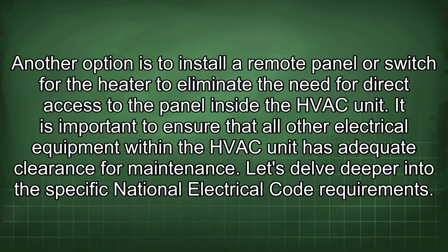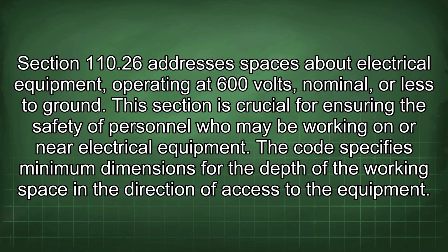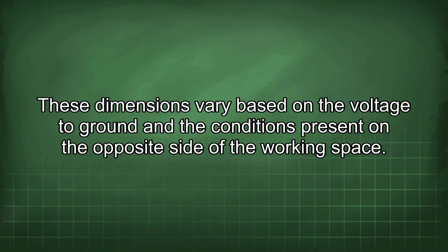Let's delve deeper into the specific National Electrical Code requirements. Section 110.26 addresses spaces about electrical equipment operating at 600 volts, nominal, or less to ground. This section is crucial for ensuring the safety of personnel who may be working on or near electrical equipment. The code specifies minimum dimensions for the depth of the working space in the direction of access to the equipment. These dimensions vary based on the voltage to ground and the conditions present on the opposite side of the working space.